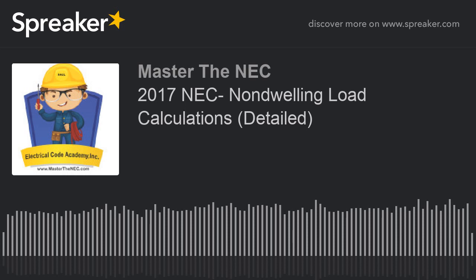Now, if both of these loads are designed to possibly be on at the same time, then guess what? Maybe you have a building where a portion of the building is supplied by a fixed electric space heating component, and another portion is air conditioning, and they might be able to run the air conditioning while the fixed electric heat is going. Then the problem with that is you'd have to count them both, because they're not non-coincident loads. They are both potentially running at the same time. So you need to keep that in mind, and you would have to equate them both.